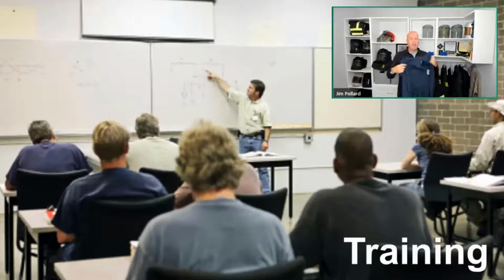coveralls. If I were to have time to show you all the details of Terry's program, it defines ESP levels. ESP is an acronym for Electrical Safety Program, and his levels are similar to Annex H, the simplified two-level system in 70E. So he'll have a level up to 8 calories, and then he'll have a level up to 65 or 75 calories. Others will go up even further because PPE does exist above 75 calories and it maxes out at 140 calories.